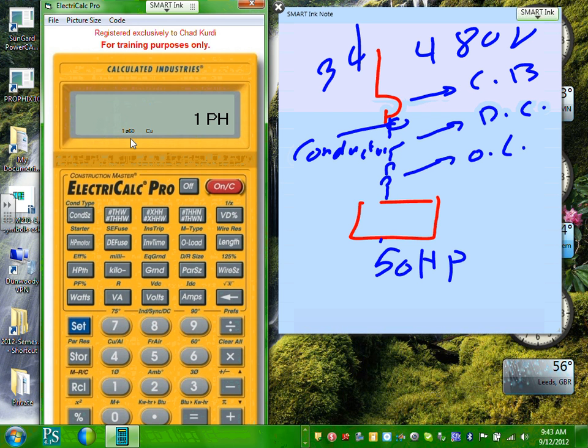Everybody's calculator set single phase 60, copper. I love copper, so I'm going to leave the copper as is. Okay, so let's take 10 horsepower. Cool, everybody, type 10 and hit the horsepower, 10 horsepower. What voltage system single phase do you guys want? Typically 240. You can't find them at less than 240.